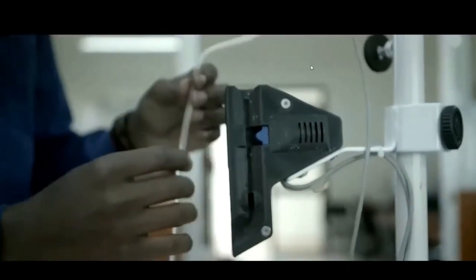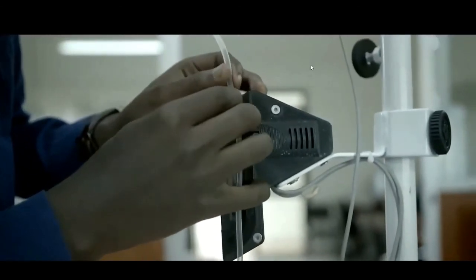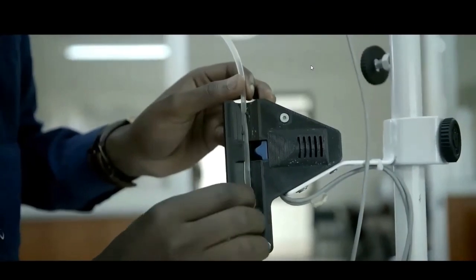We have provided for safety measures as well in terms of detection of air bubble within the tube. So we provided sensors to be able to do that. And if an air bubble is detected within the tube, the therapy is terminated, and the clinician is also provided with means to be able to flush the air bubble from the tube and resume as need be.